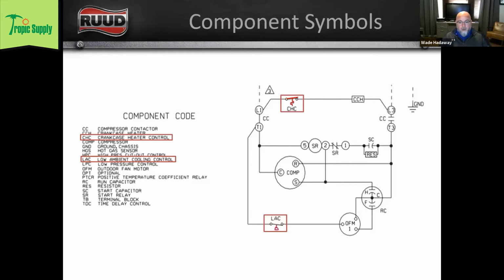Okay, low ambient control. The symbol at the bottom of the low ambient control, that little half circle, indicates that it's a pressure switch. And the way the switch is lined up with the bottom of the contact on the right...